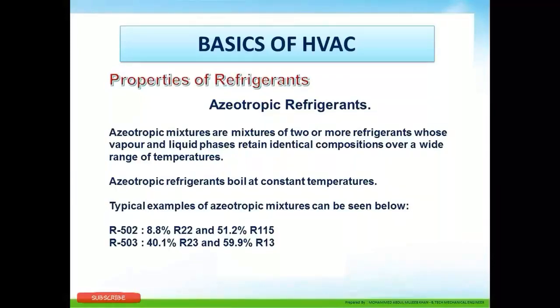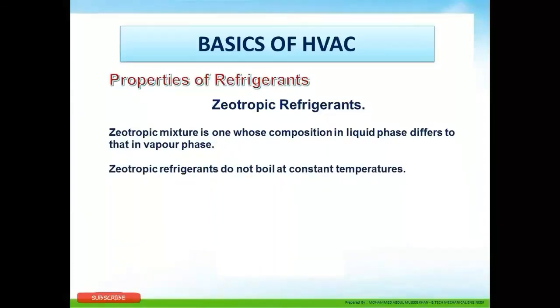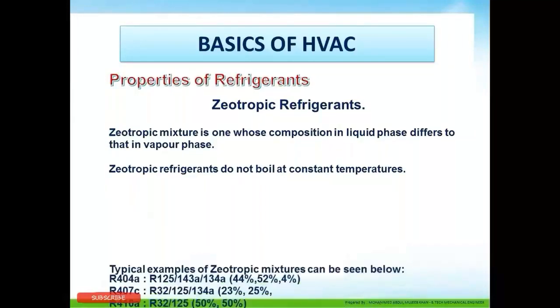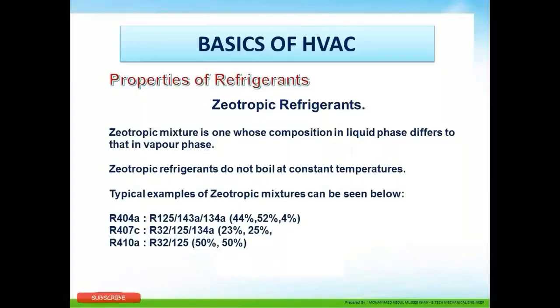R502 and R503 are mixtures of two independent refrigerants: R22 and R115, and R23 and R13. A zeotropic refrigerant is one whose composition in the liquid phase differs from that in the vapor phase. Zeotropic refrigerants do not boil at a constant temperature. Typical examples of zeotropic mixtures include R404A, R407C, and R410A.